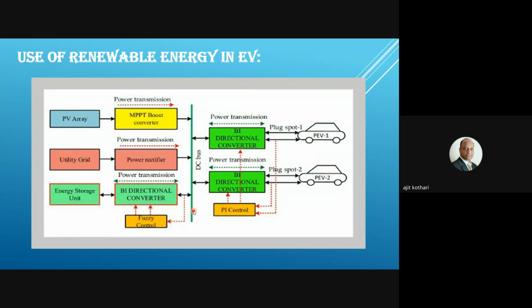Okay, I understood now. So that's the reason I was telling you this complete exercise has to be designed thoroughly. You cannot just select 200 volts because that's the PV array available. As I said, you have to start with the bidirectional charger first, because somebody has to manufacture or design the charger which works at, let's say, XYZ voltage. I'm not saying 400 is the only requirement, maybe 200 or 300, whatever voltage they are designing. That charger should be available. Once this charger is available, then the DC bus design can be done.